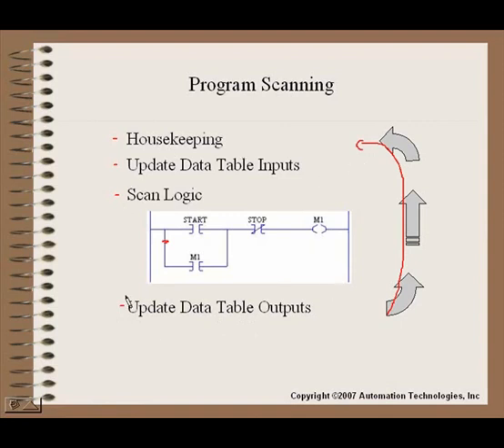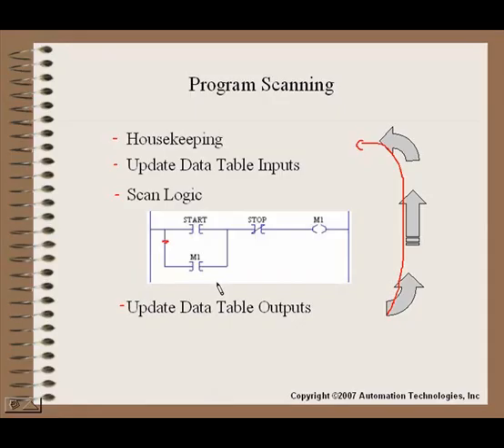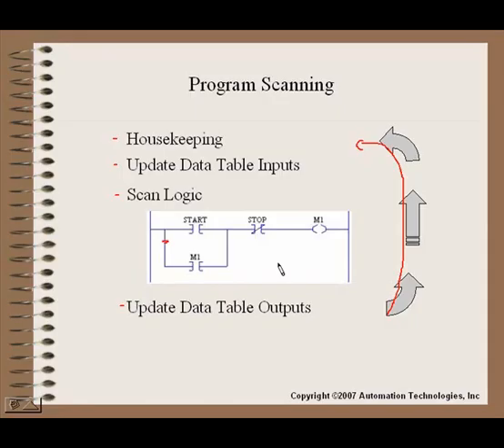This is called PLC program scan. A PLC program will scan repetitively as it's running and constantly updates its outputs, constantly checks its inputs, and that's the important thing to remember about programming in a PLC. PLC program scans are very quick. You will see them on the order of milliseconds and microseconds. So we're looking at information that's being processed very quickly and obviously has to be able to monitor relays and to be able to monitor encoders and other fast acting devices out in the field.